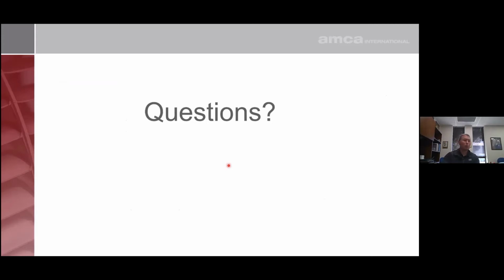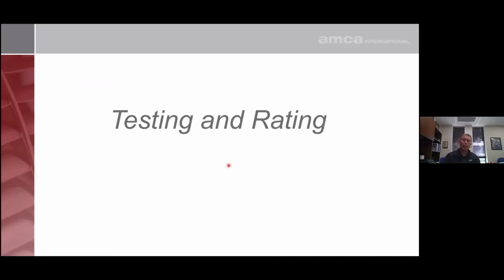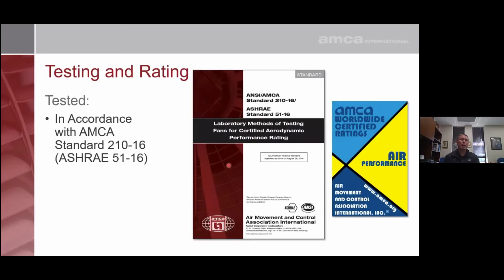Okay, so we're good on that. All right, let's talk about testing and rating of fans, which is actually a pretty important thing. Fans, at least in the North American fan market and in Asia, are typically tested in accordance with AMCA standard 210, which is also an ASHRAE standard. This gives us a methodology for how to test the fan.